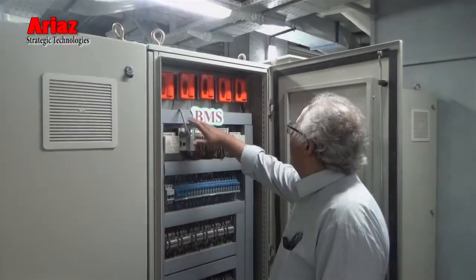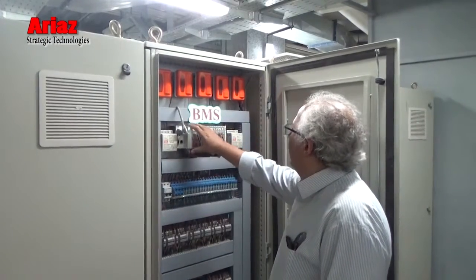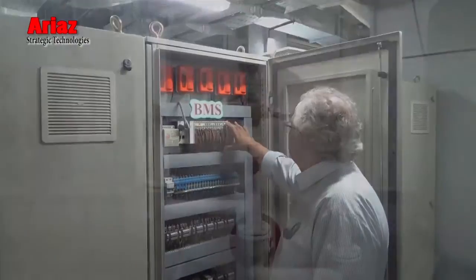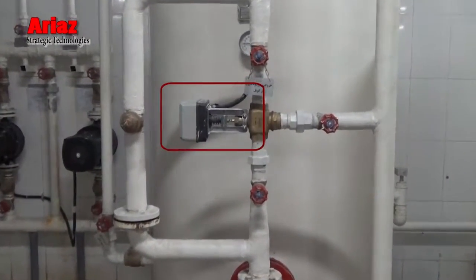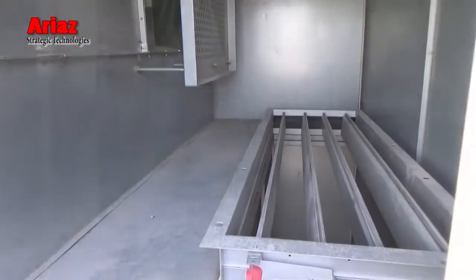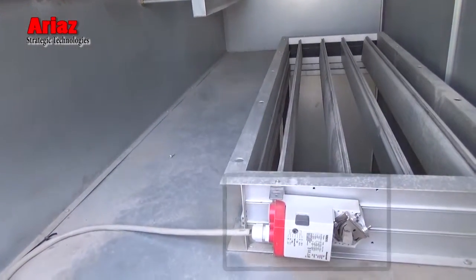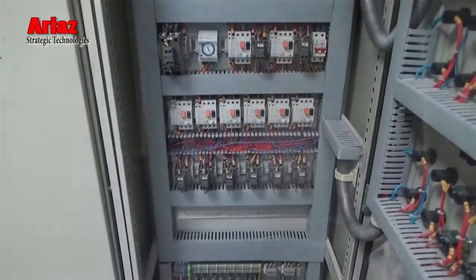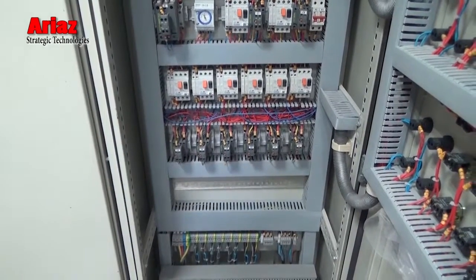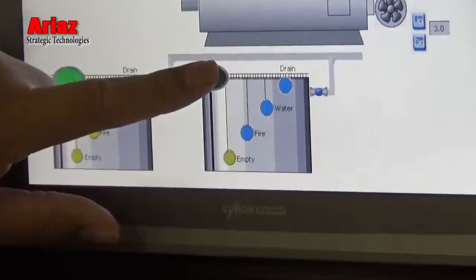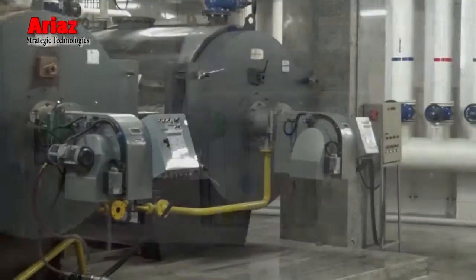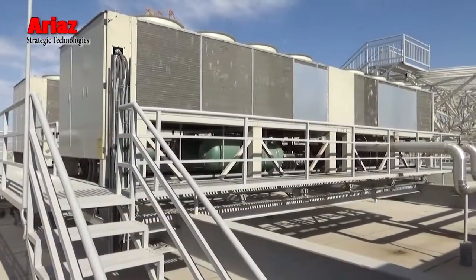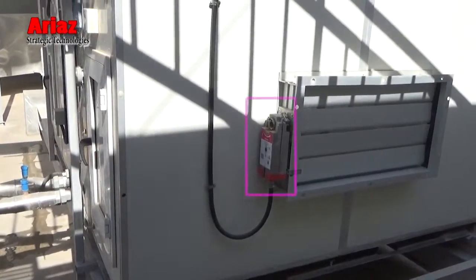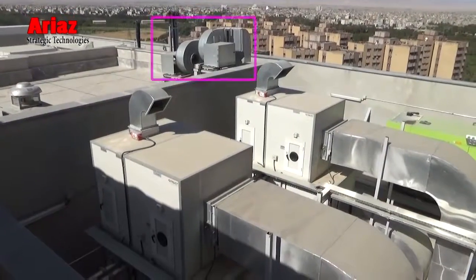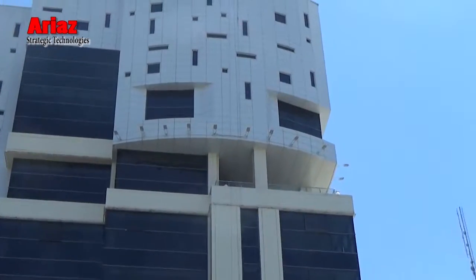As well as large orders for parts to be sent via the BMS, such as analog commands to operate the three-way valves and damper motor for mixing return air with fresh air. Digital commands for opening and closing of contactors for electric motors, two-way valves, or turning on and off the boilers, chillers, opening and closing the damper in the fresh air, exhaust fan, fan coils, communal lighting and lighting of facades.